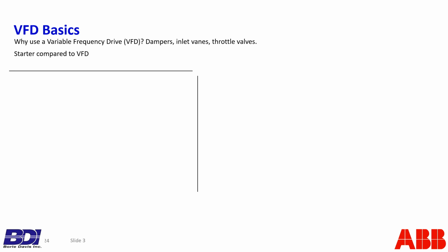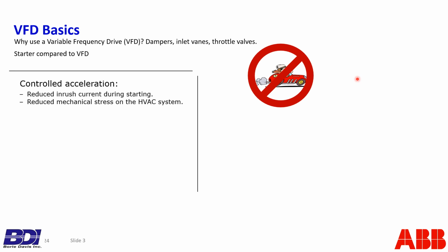So why use a variable frequency drive? Well, as opposed to variable frequency drives, the way that you would vary flow would be with dampers, inlet vanes, or throttle valves. To begin with, we'd like to compare a starter to a variable frequency drive itself. You know, in the past, starters were used, and a starter basically is just applying all the voltage and frequency to the motor at once. And if you do that, and the motor nameplate says it's a 1750 RPM motor, well, as soon as you apply the 460 volts, 60 hertz to the motor, it's going to try and jump to speed, jump to 1750 RPM, and that's going to create a lot of inrush current.